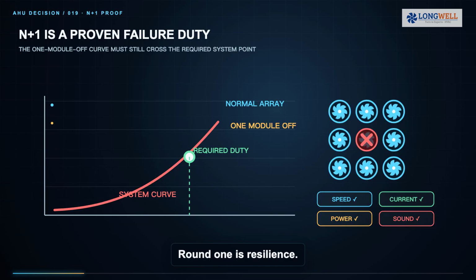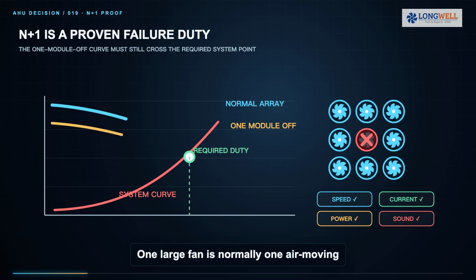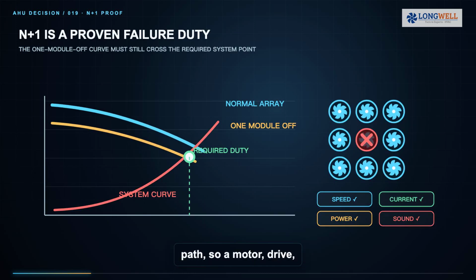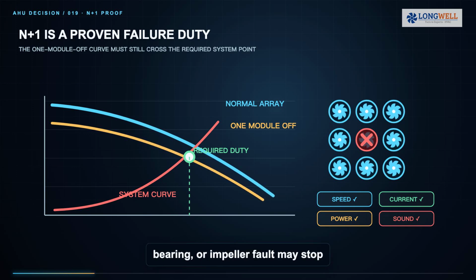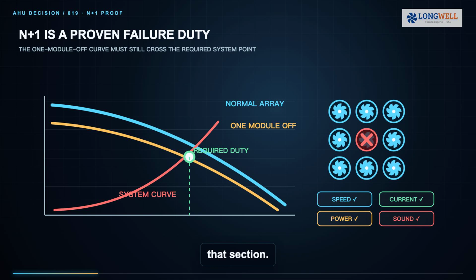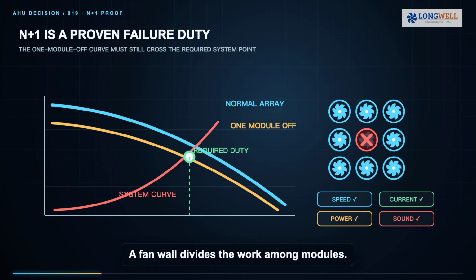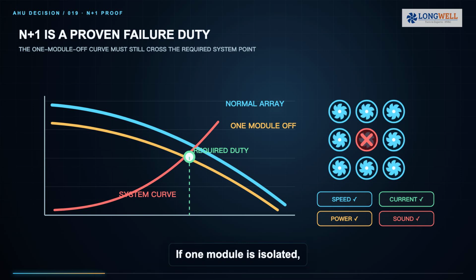Round 1 is resilience. One large fan is normally one air moving path, so a motor, drive, bearing, or impeller fault may stop that section. A fan wall divides the work among modules. If one module is isolated, the others may continue. But true N+1 capacity is proven only when the one module off array curve still reaches the required system duty point without exceeding speed, current, power, or sound limits. An unused square in the wall is not proof.